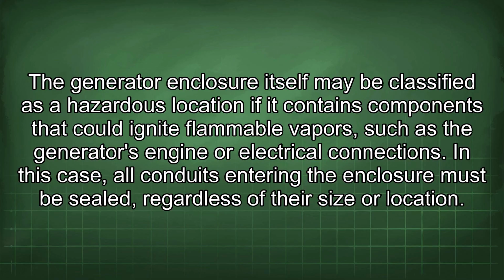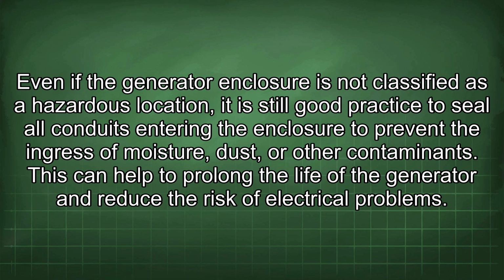In this case, all conduits entering the enclosure must be sealed, regardless of their size or location. Even if the generator enclosure is not classified as a hazardous location, it is still good practice to seal all conduits entering the enclosure to prevent the ingress of moisture, dust, or other contaminants. This can help to prolong the life of the generator and reduce the risk of electrical problems.